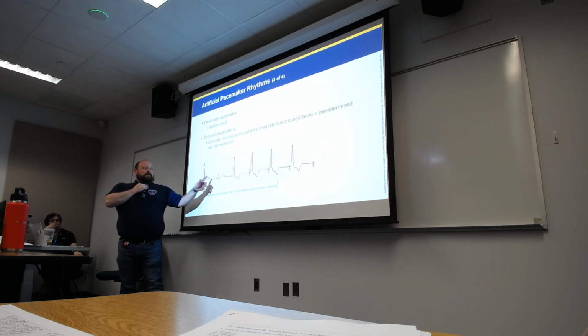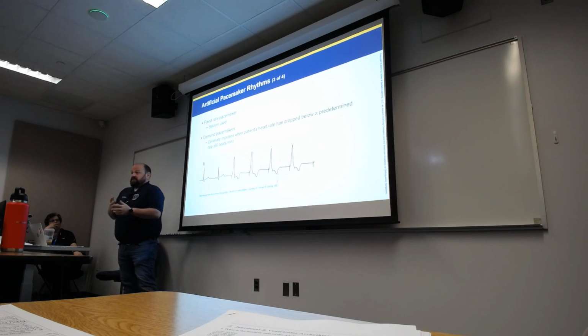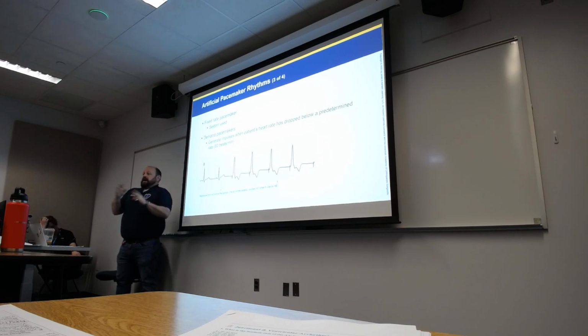This pacemaker only will fire as the patient needs. So if the rate drops below 60, you'll start seeing pacer spikes. If you look at our transcutaneous pacers that we use, they do the same thing, right? If it senses R to R waves, it will not overdrive pace. It won't go higher than their rate.